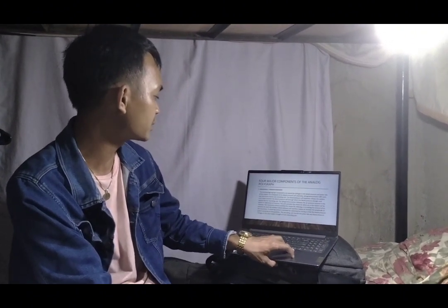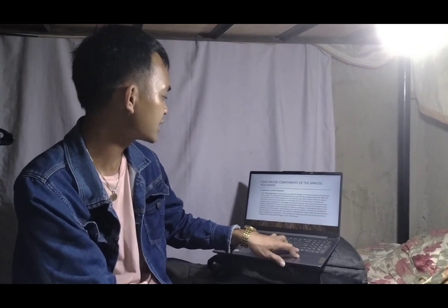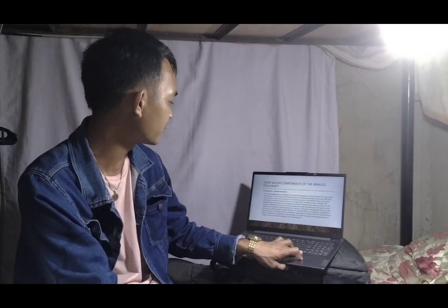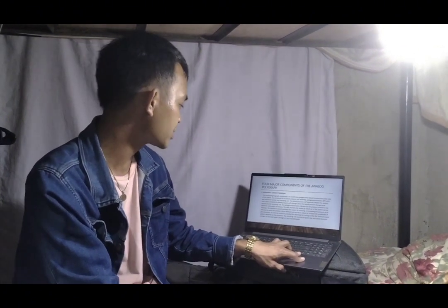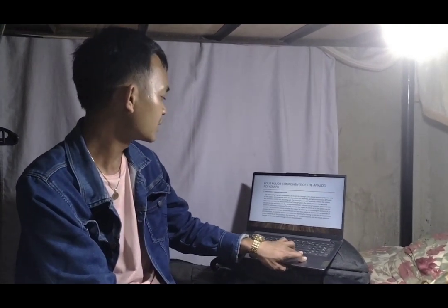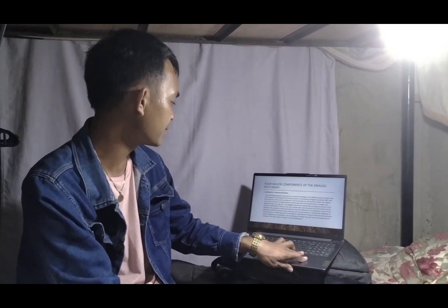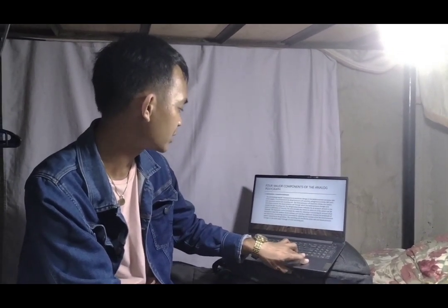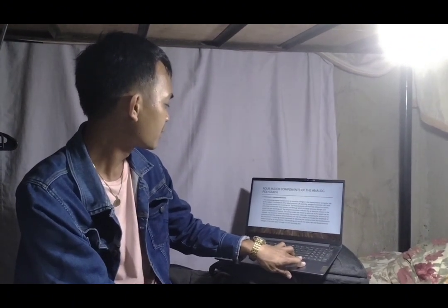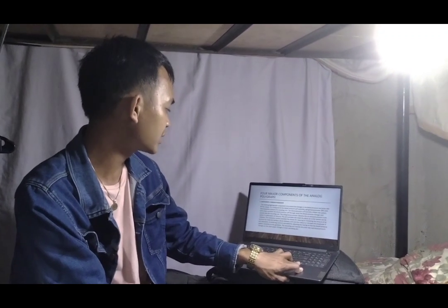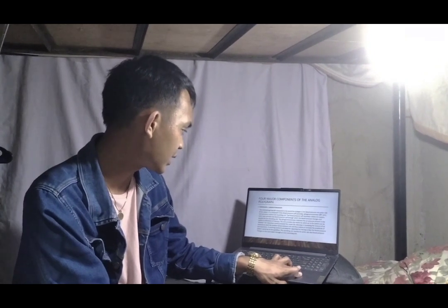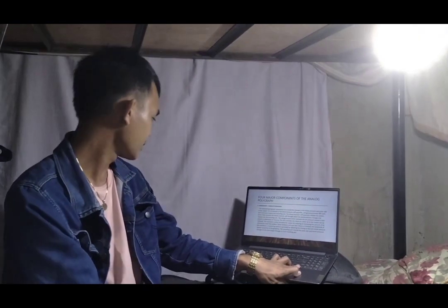The sphygmomanometer indicates the air pressure present in the system in millimeters of mercury. The vent provides a means by which air in the system can be released. The resonance control provides the means of reducing or increasing the amount of air pressure reaching the tambour bellows unit, thus reducing or increasing the amplitude of pen excursion.